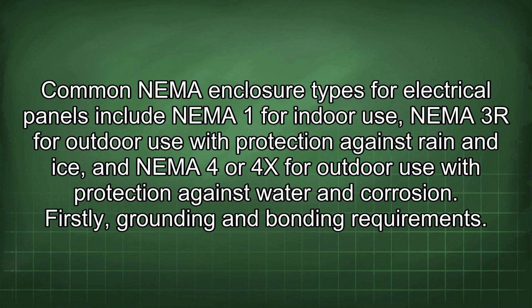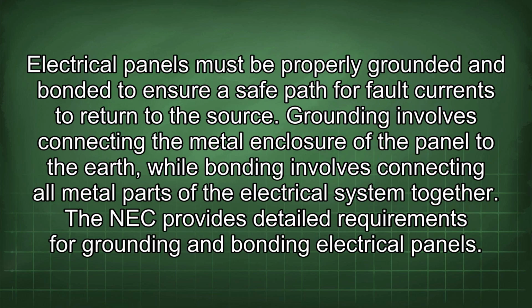Firstly, grounding and bonding requirements. Electrical panels must be properly grounded and bonded to ensure a safe path for fault currents to return to the source. Grounding involves connecting the metal enclosure of the panel to the earth, while bonding involves connecting all metal parts of the electrical system together. The NEC provides detailed requirements for grounding and bonding electrical panels.